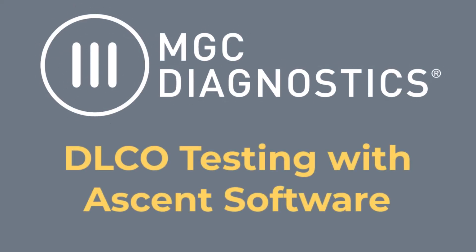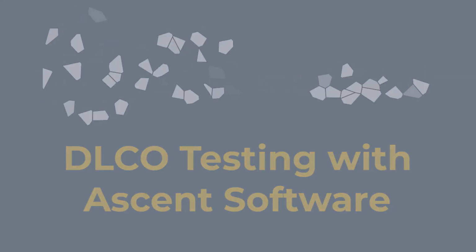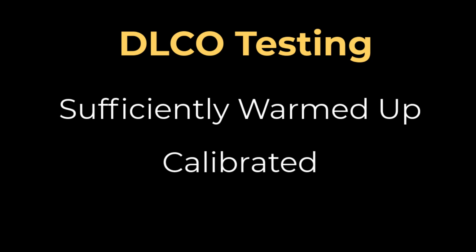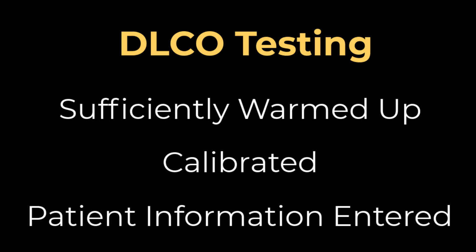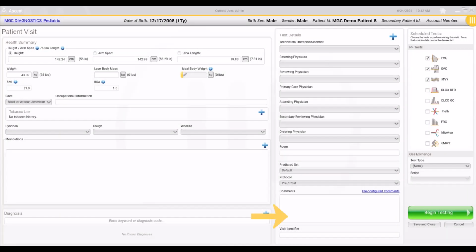In this video, we will discuss how to perform DLCO testing with Ascent cardiorespiratory software. This video presumes that the system is sufficiently warmed up, calibrated, and patient information has already been entered.